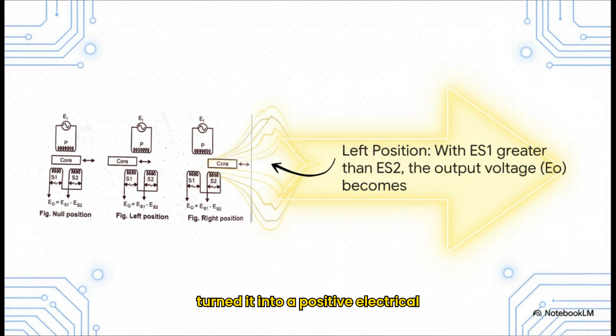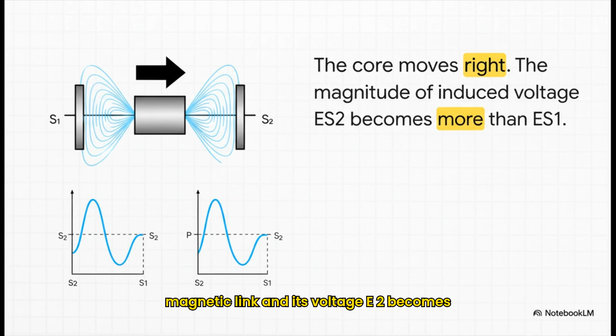How cool is that? And I'm pretty sure you can guess what happens next. If the core moves to the right, the exact opposite happens. Now it's closer to the second coil, S2. So it gets the stronger magnetic link, and its voltage, ES2, becomes bigger than ES1. And when we calculate our output again, ES1 minus ES2, we're now subtracting a bigger number from a smaller one. So what do we get? A negative number. A movement to the right creates a negative signal. This is brilliant. The LVDT doesn't just tell us that something moved, it tells us which way it went.